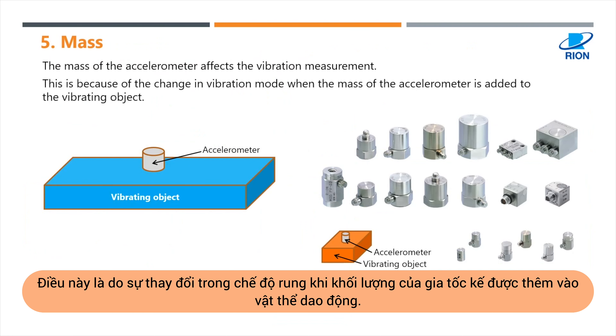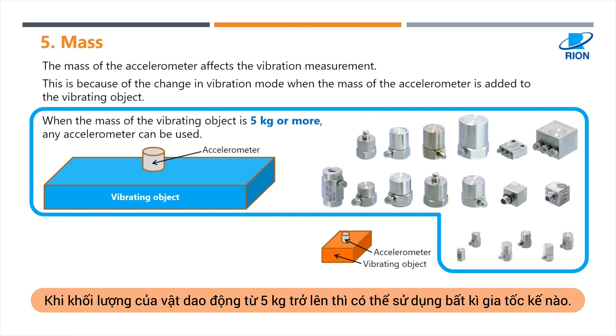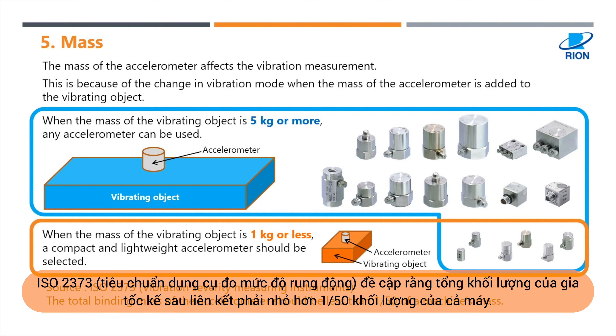Number five: mass. The mass of the accelerometer affects the vibration measurement, because of the change in vibration mode when the mass of the accelerometer is added to the vibrating object. When the mass of the vibrating object is 5 kilograms or more, any accelerometer can be used. When the mass of the vibrating object is 1 kilogram or less, a compact and lightweight accelerometer should be selected. ISO 2373, Vibration Severity Measuring Instruments, mentions that the total binding mass of the accelerometer should be less than 1/50th of a machine's mass.